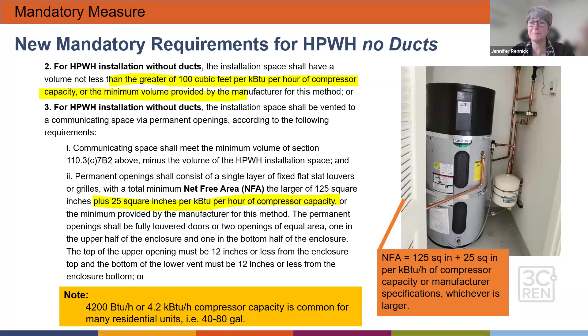And in case you need to do some rough sizing, for most of the residential units that are 40 to 80 gallons, a lot of them have a compressor capacity of 4.2 kBTU per hour. So you can take that 4.2, multiply it by 100, and that gives you 420. Well, most manufacturers, even the best right now, are recommending 450 cubic feet. So even though they've given you this formula and the option, you still have to use the greater of that formula or the volume provided by the manufacturer. So in most cases, you cut to the chase and follow the manufacturer's recommendations. And even though that typically was a guideline, it's now a mandatory requirement that you follow the manufacturer's guidelines.